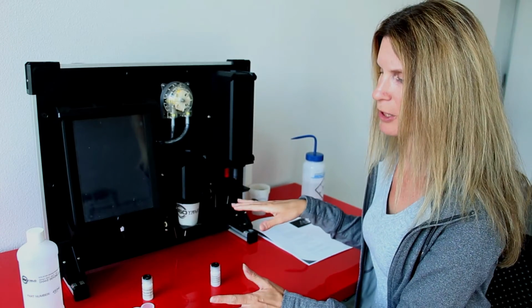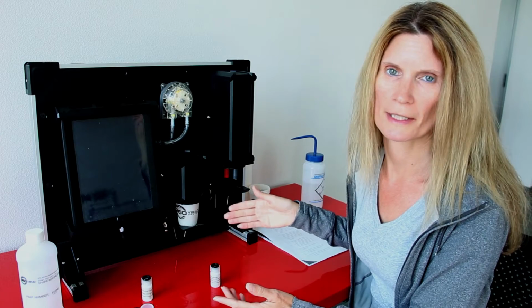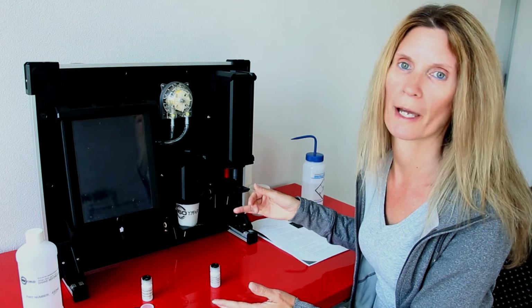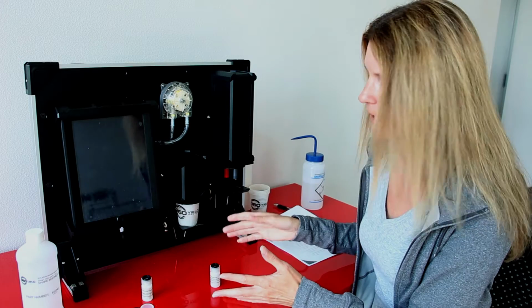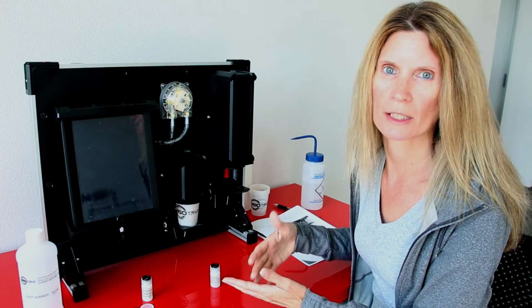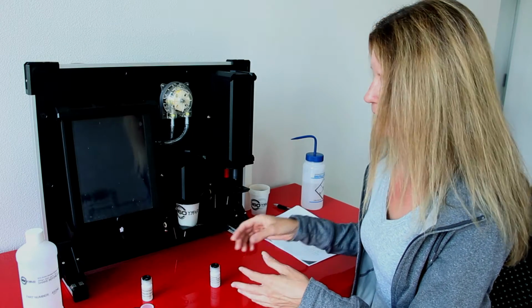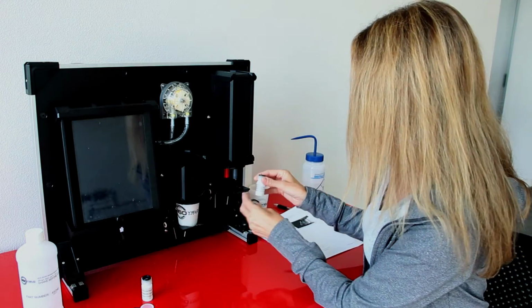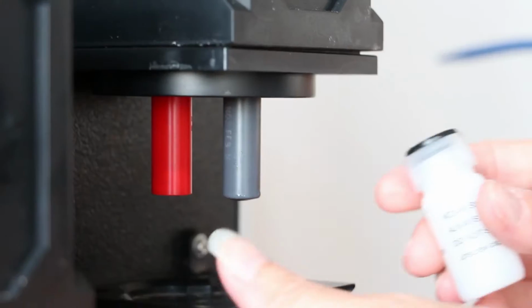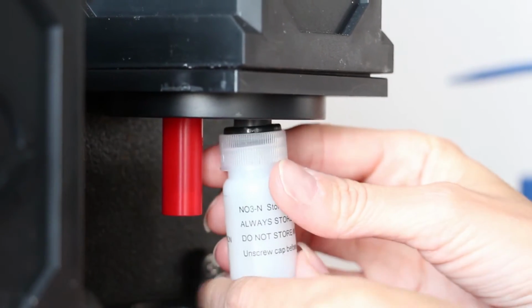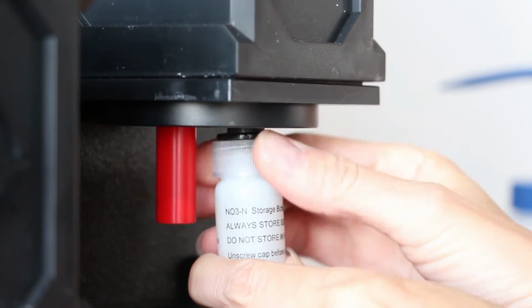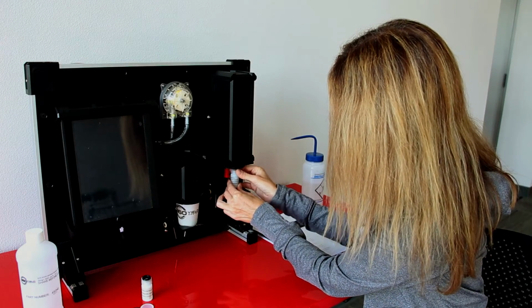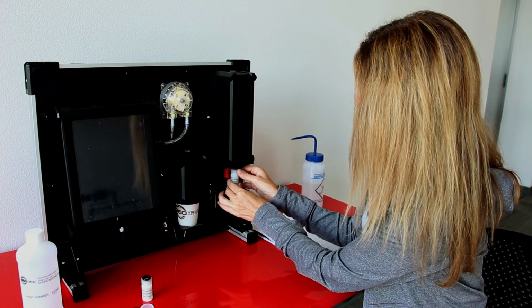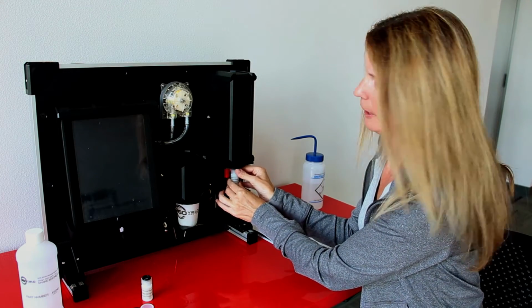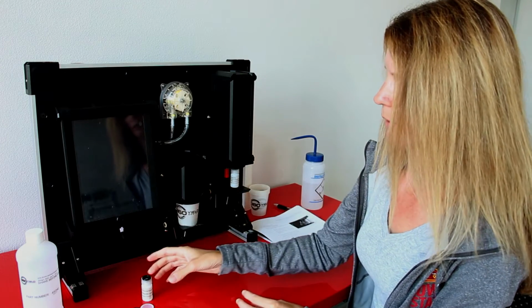Now, when I remove the calibration bottle, I'm not going to worry about rinsing and drying it off. If this sensor is a little wet going into storage, that's fine. It can have a moist environment. We just don't want it to be soaking in any standard solution or any distilled water. So that bottle should stay empty and in a dry environment that way. So what we're going to do is just unscrew this cap a little bit so it's easier to get on, and just slide it up so it's about half an inch from the top there, and then screw the cap right on there tight. We don't want to let any air in there or any other debris that might come with it as well.